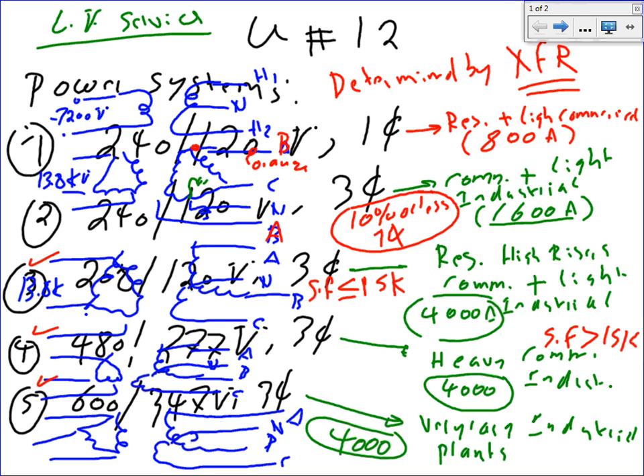There's nothing that says you can't have a 10,000 square foot commercial building and bring 480 to it. There's nothing. The idea, guys, is that if you have larger than 15,000, the building is large enough to justify the price of 480 switchgear.